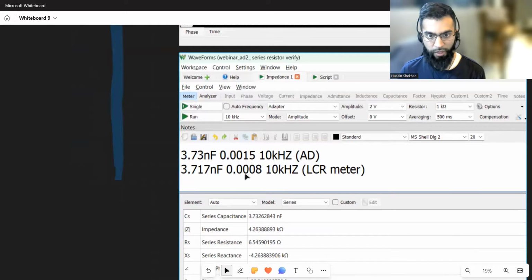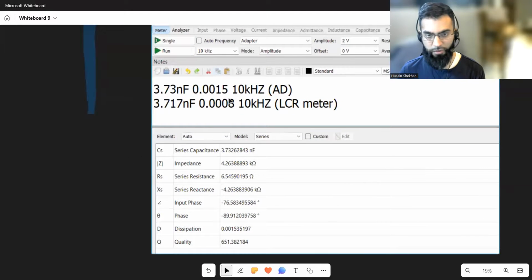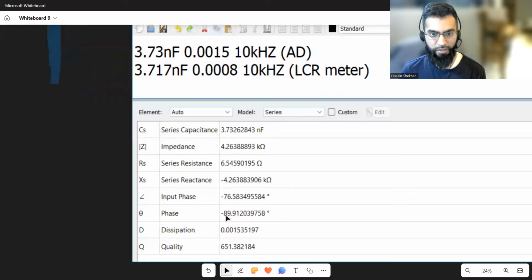However, the LCR meter gave me 0.0008. This difference can be significant if you assemble many transducers and you get this difference in values. So it's important to be able to track. And here you see the phase is negative 89.91. So the requirement to measure very accurate phase values is too high for this specific device in terms of accuracy and noise level.